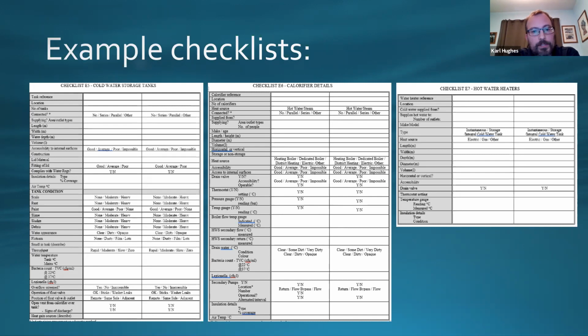And then you've got the calorifiers in the middle section there, again detailing the make and model, what it does, whether it's compliant, whether it's got a boiler flow primary coil going through it, making sure that's working. You take a drain sample from the drain water to see whether that's clear or not, and things like that as well. See whether it's got a secondary pump. Usually you'll see the secondary pumps on the flow and return systems, and the installation details. The hot water heaters are the lesser ones there, so there's less detail that you have to take than the calorifiers, but still you've got to make sure that they're doing what they should be doing and why they're doing what they're doing. So we'll go to the next one.